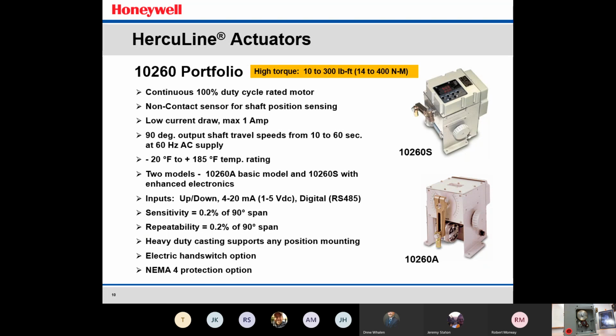We discussed a little bit about the inputs. Again, you can have up and down, which is just a relay input into the actuator to drive it up or down, or 4 to 20 milliamp. Also, you can control these with a digital RS-485 communication link. This is Modbus communications, and it is a two-way communication. So you can gather information from the actuator back at the PLC, SCADA system or recording device, and you can also control the actuator through this communication link as well. It is Modbus RS-485 communications, so basically a three-wire connection to the actuator to allow that communication to happen.